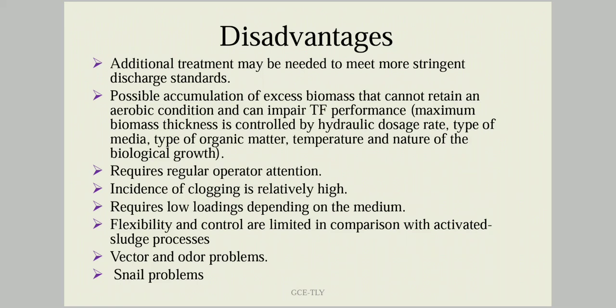Some disadvantages of the system are: the effluent needs additional treatment to meet stringent disposal standards. Accumulation of biomass can impair filtration performance under aerobic conditions. It requires regular operational attention, and the possibility of clogging is high due to biological growth. It requires low loadings depending on the medium. Flexibility and control are limited in comparison with the activated sludge process, and there are problems of odor, vectors, and snails.